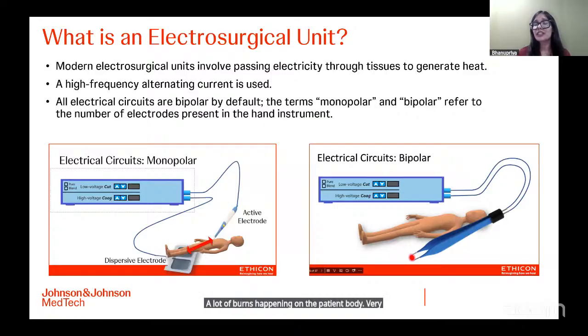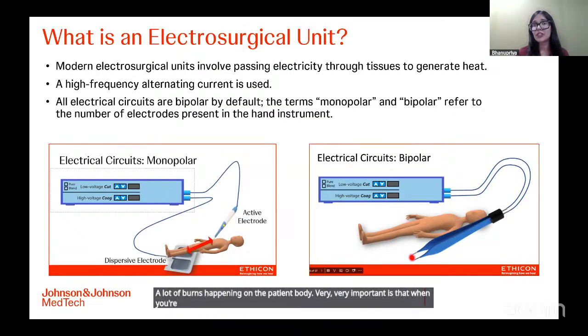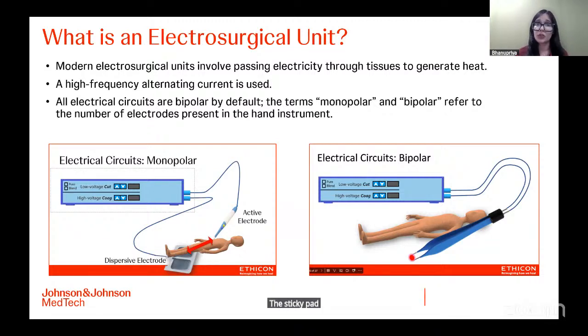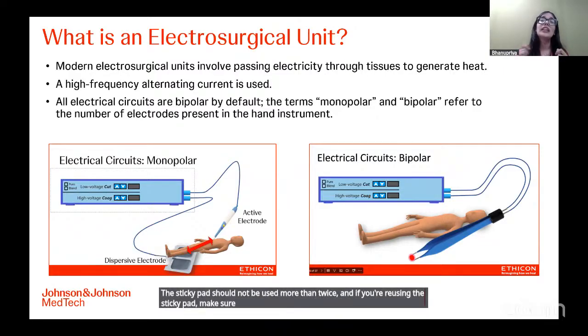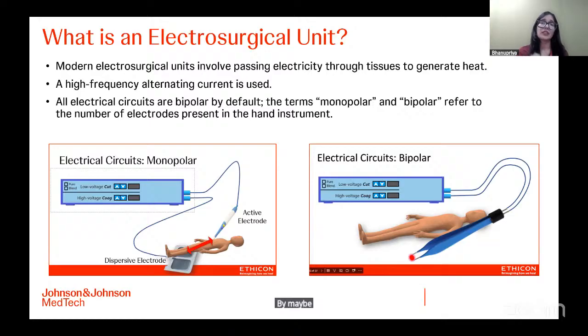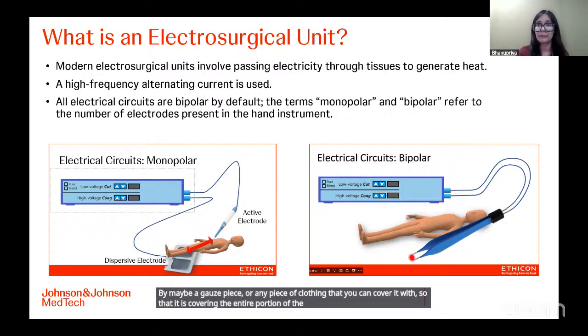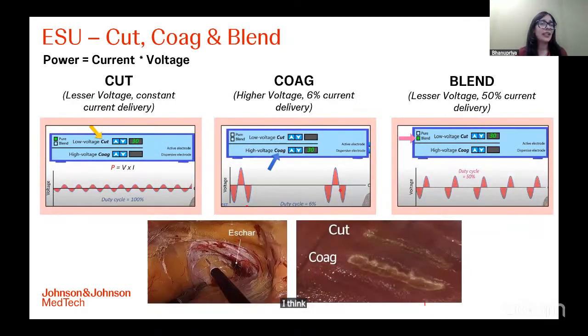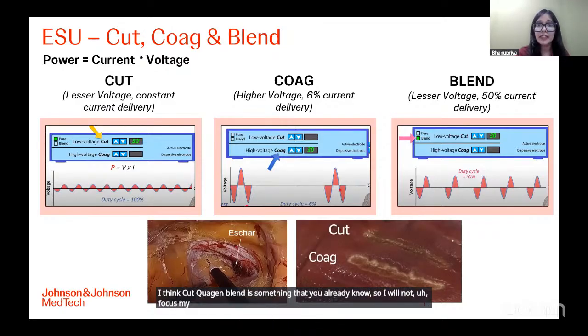Very, very important: when you are using an electrosurgical unit, because there is current flowing through the body of the patient, the sticky pad should not be used more than twice. And if you are reusing the sticky pad, make sure that it is fully covered by maybe a gauze piece or any piece of clothing that you can cover it with, so that it is covering the entire portion of the patient body. I think cut, coag, and blend is something that you already know, so I will not focus my time and attention on this.